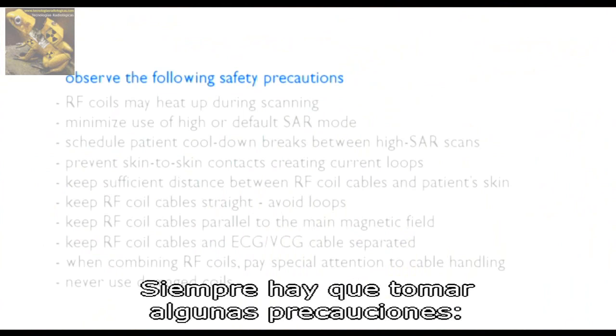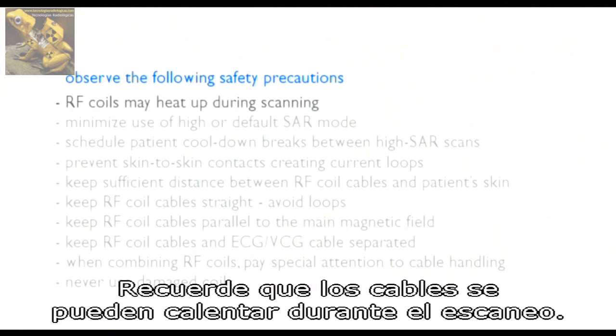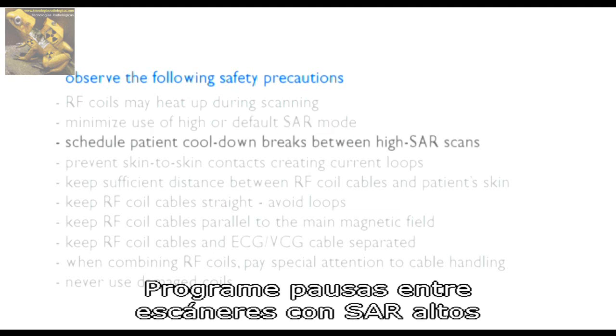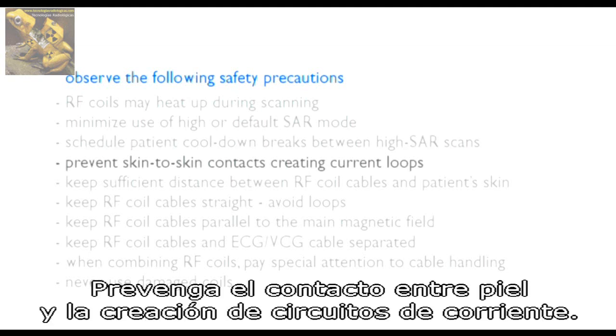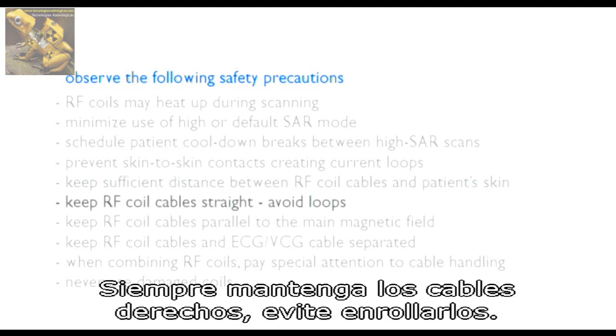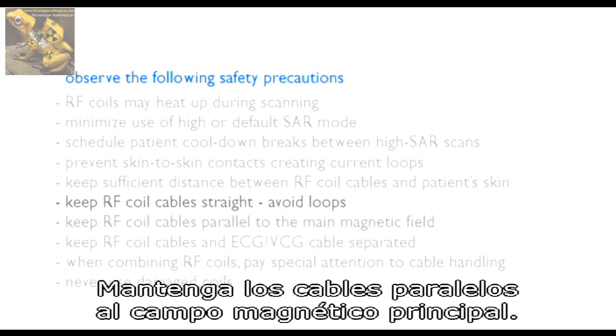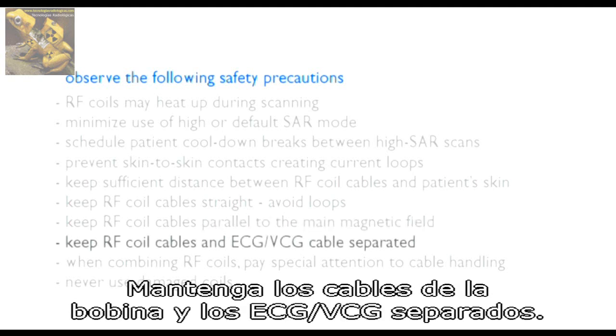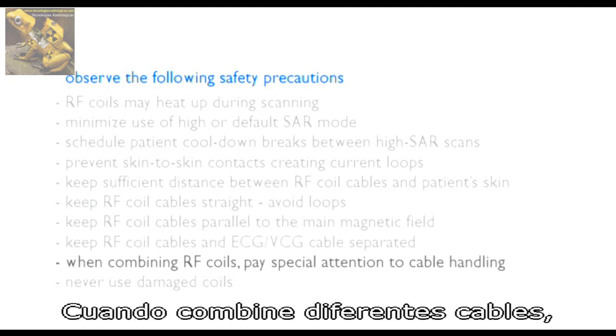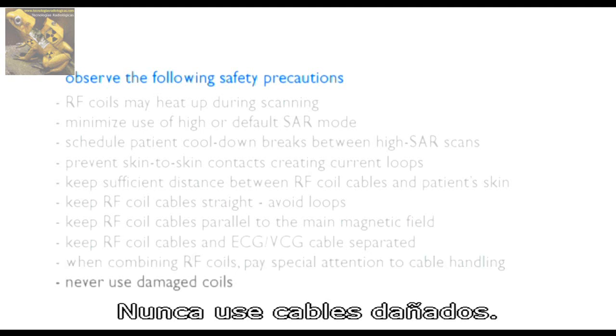Some safety precautions should always be observed: Remember that RF coils may heat up during scanning. Minimize the use of high or default SAR mode. Schedule patient cool-down breaks between high SAR scans. Prevent skin-to-skin contacts that create current loops. Keep sufficient distance between RF coil cables and the patient's skin. Keep RF coil cables straight and avoid loops. Keep RF coil cables parallel to the main magnetic field. Keep RF coil cables and ECG/VCG cables separated. When combining RF coils, pay special attention to cable handling. Never use damaged coils.